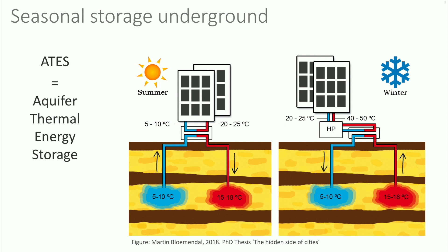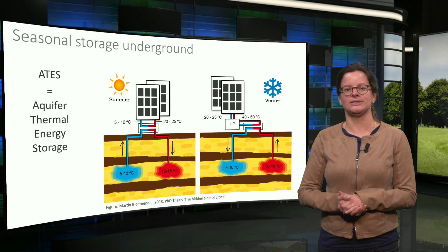In winter, the reverse happens. Warm water from the warm well is extracted to be used for heating the building. Since the water stored usually has a maximum temperature of 25 degrees, a heat pump is used to further upgrade the temperature. The cooled groundwater is injected in the cold well again. On an annual basis, the heat and cold extracted must be in balance.